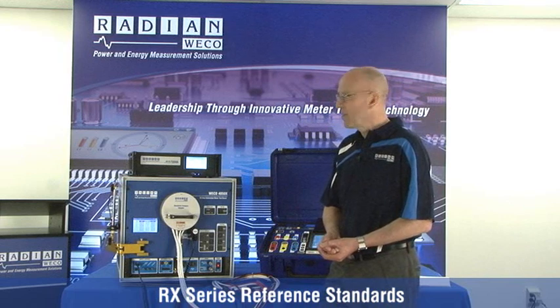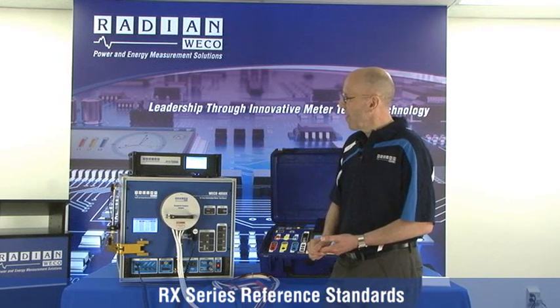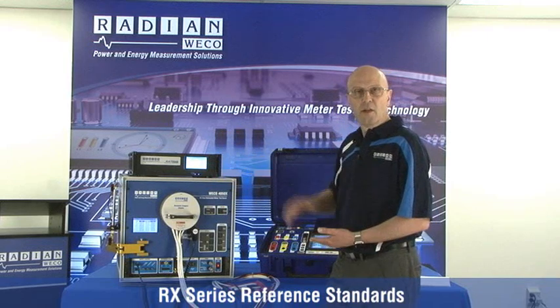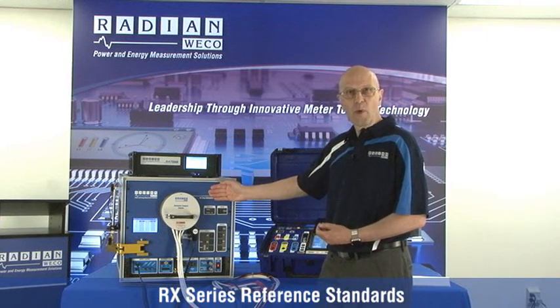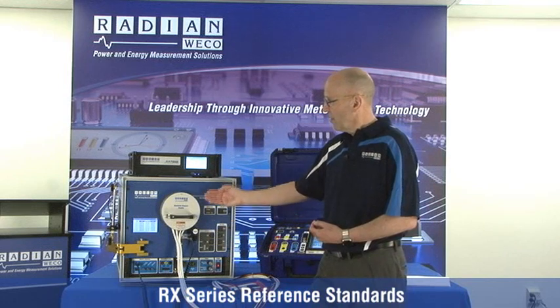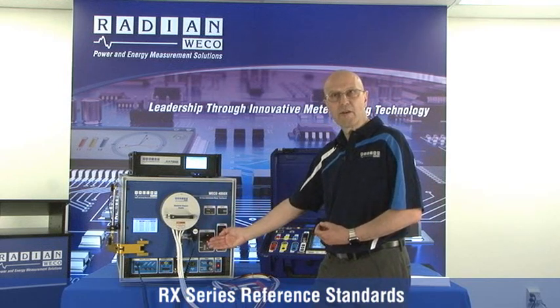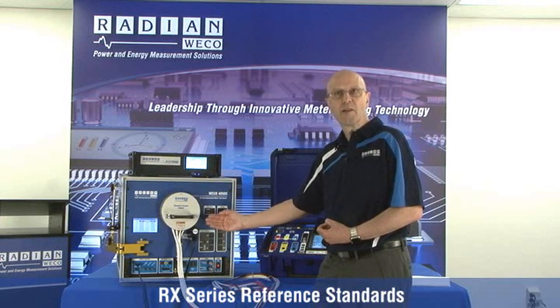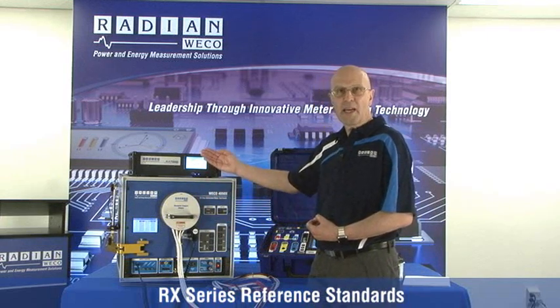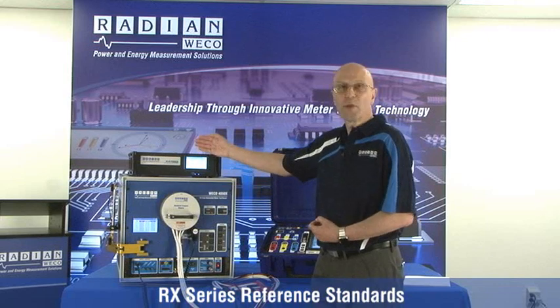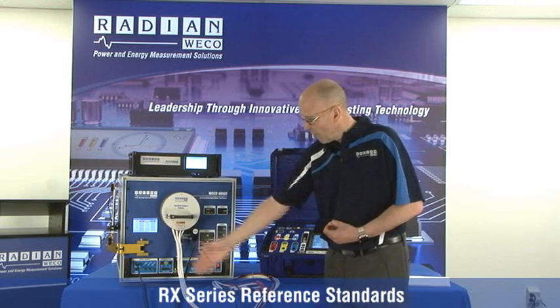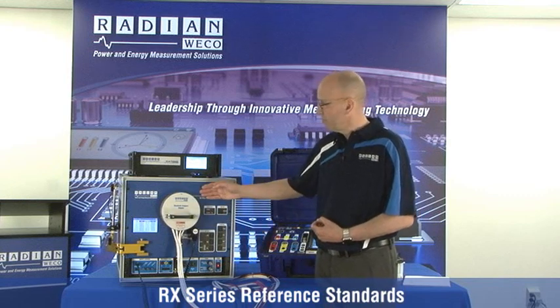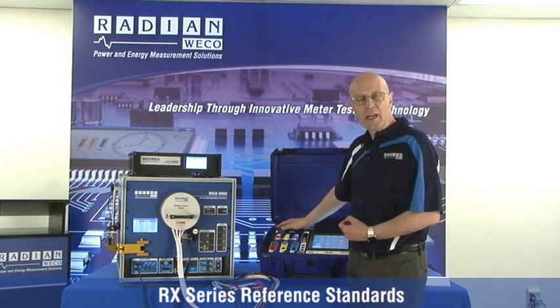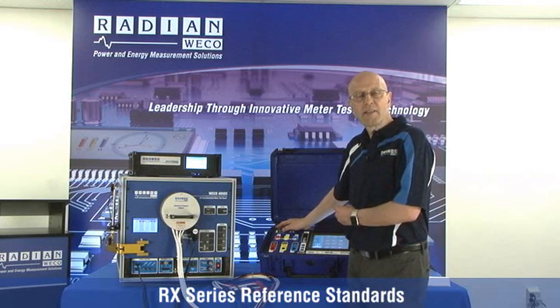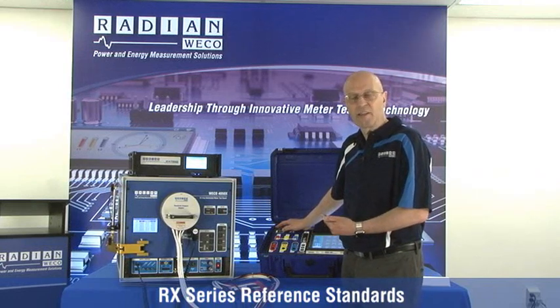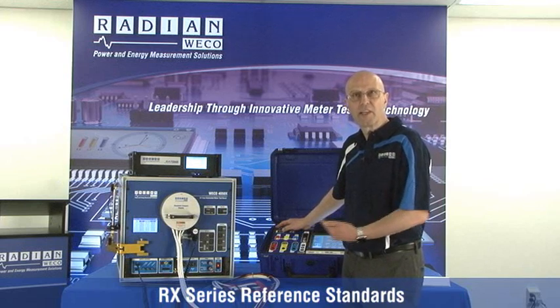For applications of reference standards, they are used as a reference for calibrating other devices, or you will find them embedded within the device itself. So for example, the 4000 series actually has an RX or an RD standard built inside that we can intercompare the measurements of that internal standard to the external standard. We do this by using a range of standards compare adapters. Similarly with our site analyzer products, the embedded standard is compared with an external calibrated standard, again using intercomparison connection cables.